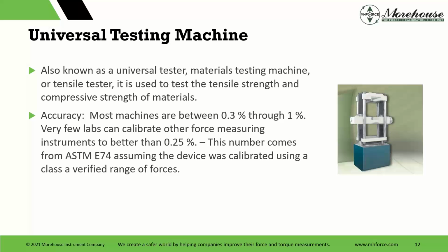Then there are these other machines, universal testing machines, which people use for calibration, and maybe they shouldn't, maybe they can. This is a trade-off, right? It's a materials test machine, and it's used to test tensile strength and compressive strength of materials. Most of these machines are designed to be 0.3% through 1%. Very few labs can calibrate other force measuring instruments to better than 0.25%. This number comes from E74, assuming the device was calibrated using a Class A verified range of forces.